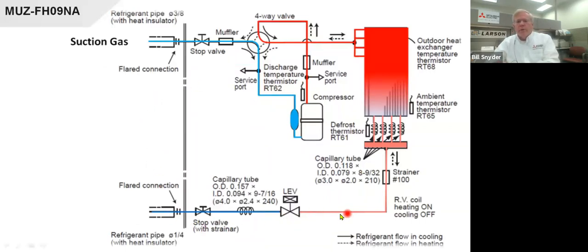non-hyperheat, just standard unit. We come out of the compressor, we're still monitoring the temperature coming out of the compressor through a muffler. These units are extremely quiet. That's one of the reasons the linear expansion valve is in the outdoor unit, so we don't hear any hissing and all as the refrigerant expands. We expand and start doing that in the pipe going to the indoor unit, so it makes it quiet.